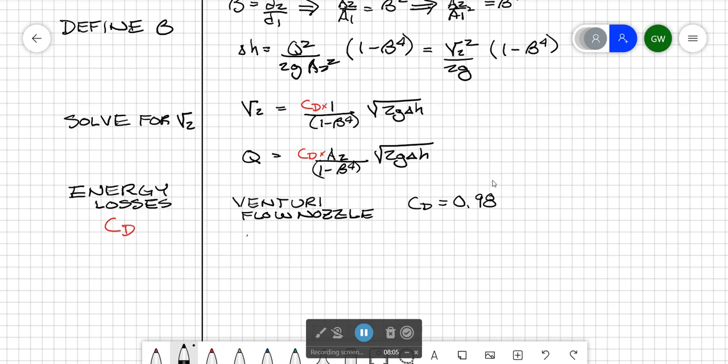If we have an orifice, very inefficient at contracting flow, so our cd value drops to about 0.60. These values remain pretty constant as long as you've got high velocity, relatively large pipes, and low viscosity fluid.